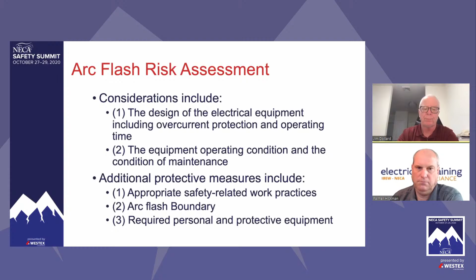And additional protective measures would include appropriate safety-related work practices, and they will be the employer's work practices, the arc flash boundary, and any required personal protective equipment. Now, Palmer mentioned the estimate of likelihood table of an arc flash occurrence, and that's Table 130.5(C). And here's just a little piece of it.